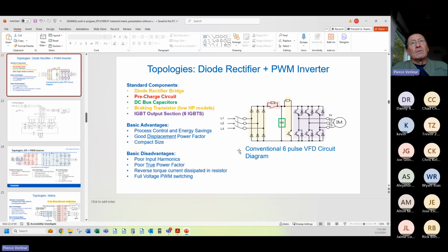Early variable frequency drives were very rough on the motor, could not produce more than a 6-to-1 speed range, and had a difficulty doing 6-to-1 constant torque. So for the most part, they were put on fans and pumps, and they were promoted as a great tool for energy savings, as VFDs have always been promoted and still are today, because you now could vary the speed of the fan or the pump to create the flow that you needed and reduce the power of the motor in doing so, reducing power draw. It was touted as a huge energy savings tool. Great technology for the day.